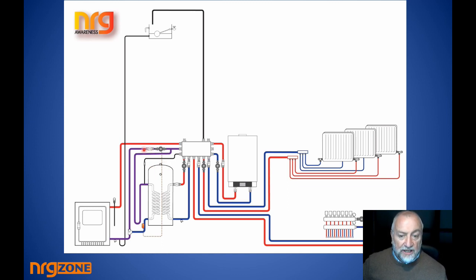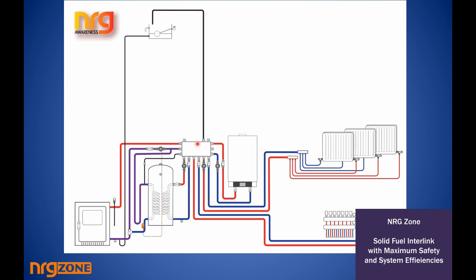assistance of pumps, you have to understand pipe sizing, gravity circuit, deaeration, because it doesn't have all these modern fandangos to get rid of all of the issues, like boilers that deaerate themselves and whatever, and also pumps that regulate themselves. So in this scenario we have a 100% open circuit from the solid fuel appliance to the hot water cylinder. Let's follow it. Flow comes up, goes through the manifold. You already know there's no obstruction, travels across the top chamber, goes over the top chamber, round through the bypass, completely open, no resistance, and it gets to this point.